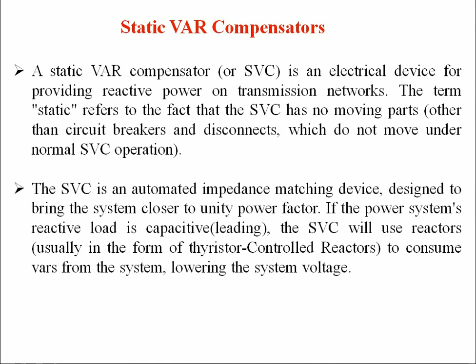If the power system's reactive load is capacitive, the SVC will use reactors, usually in the form of thyristor controlled reactors, TCRs, to consume the extra vars from the system, which lowers the system voltage. And under the inductive conditions, that is lagging conditions, the capacitor banks are automatically switched in, thus providing a higher system voltage.